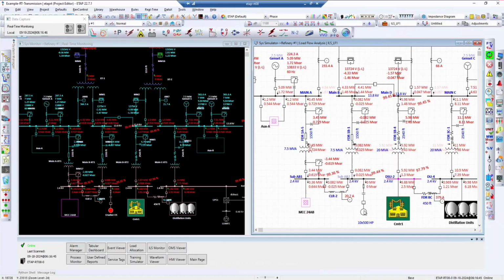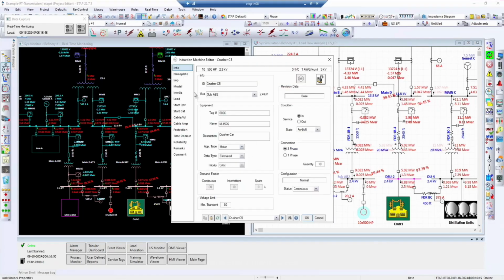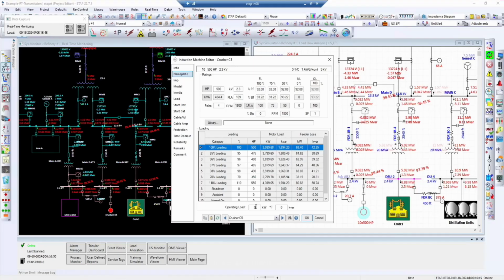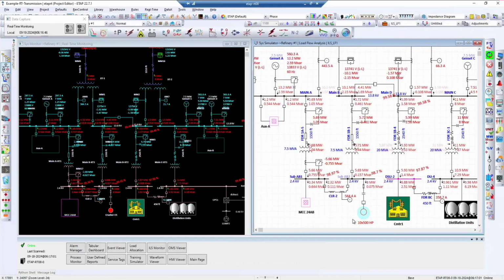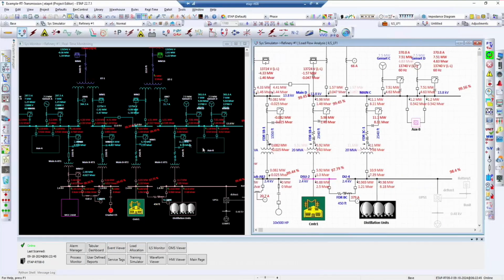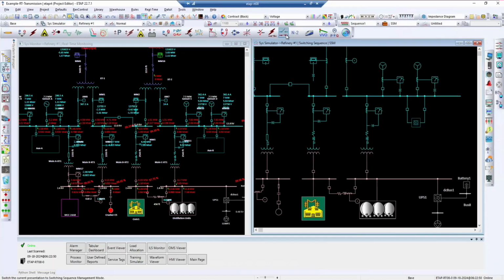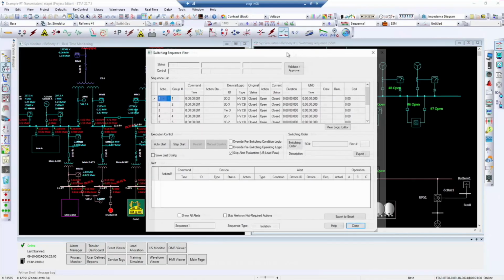Using ETAP load flow, I can also evaluate for planning purposes the effect of increasing the amount of load in a component. Before we run the load flow analysis, we can update the component with a planned increase in load. Protection and coordination can also be evaluated using transient stability, where I can simulate the effects of opening a tie breaker for maintenance or evaluate how it will impact the system. In this case, we can set up a condition where after 100 milliseconds, the circuit breaker is open. Once we run the scenario, we can see that after a few seconds, the bus will be tripped because of an overcurrent relay detecting the fault.